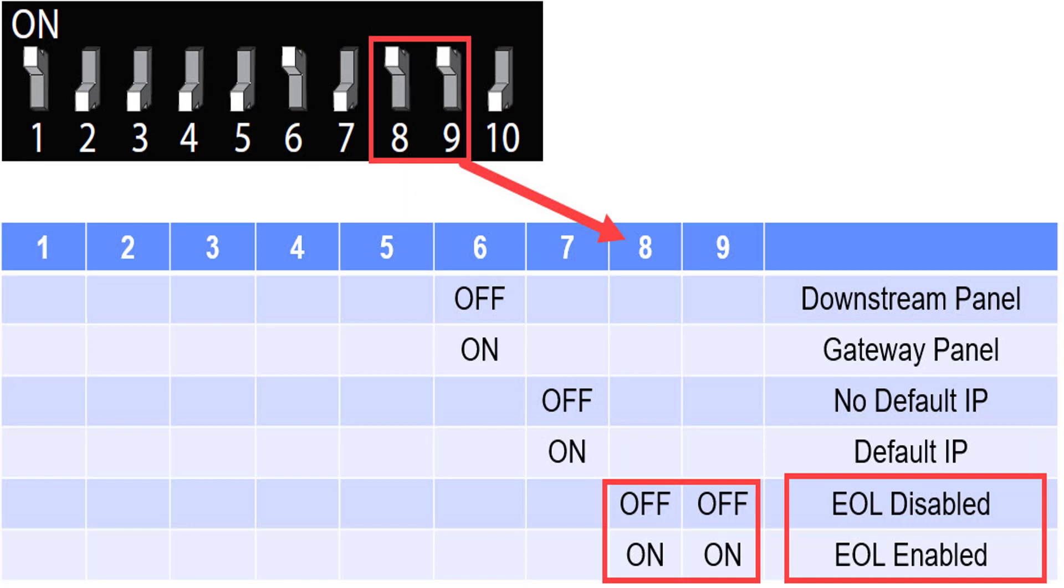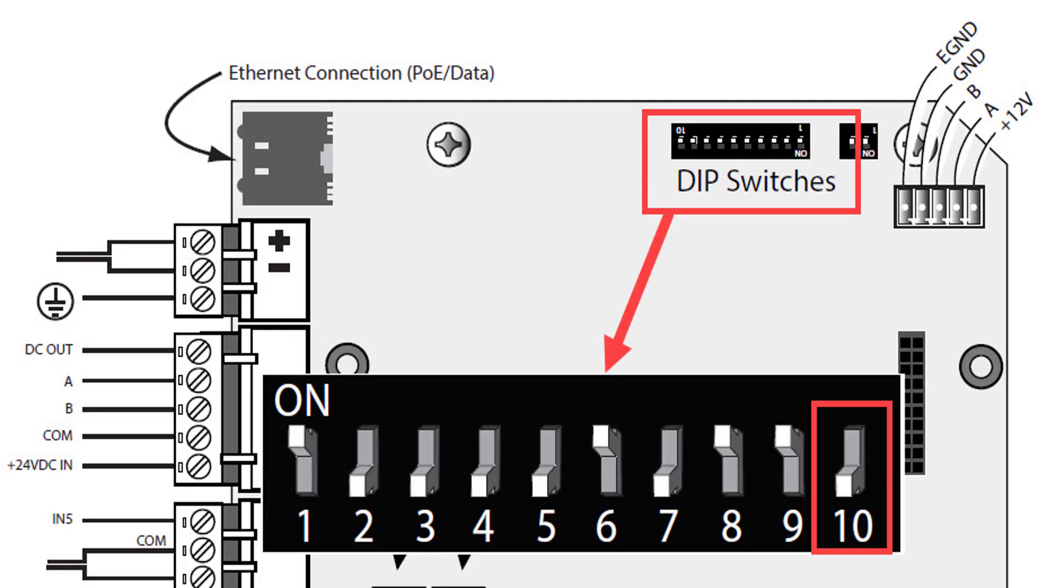DIP switches 8 and 9 set the panel as an end of the loop device. They must be on on a standalone panel or the first and last panels of a 485 loop.